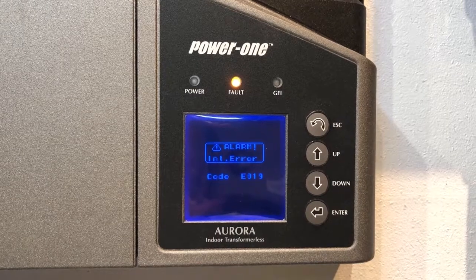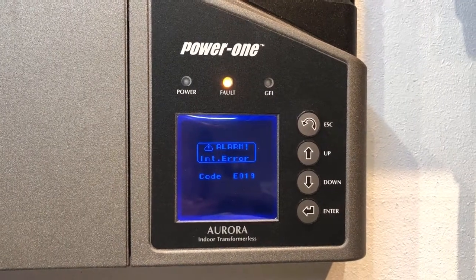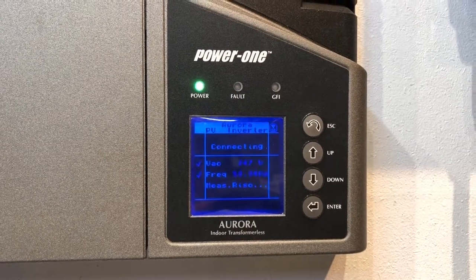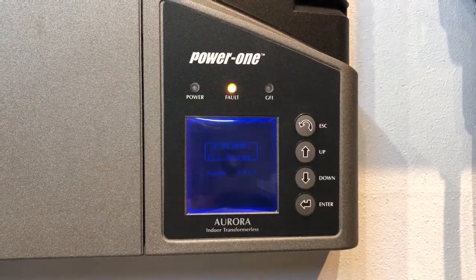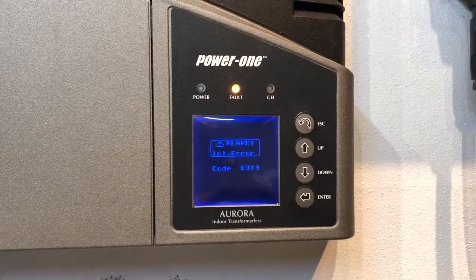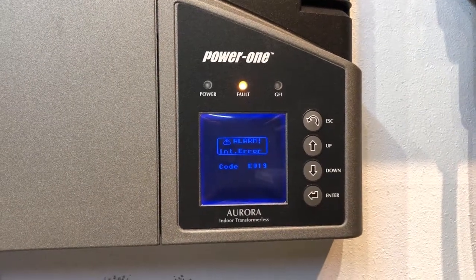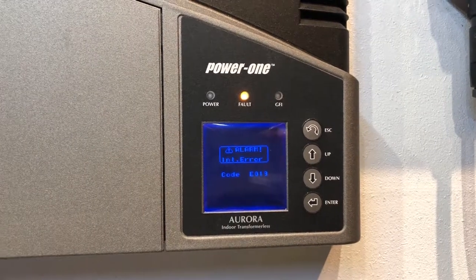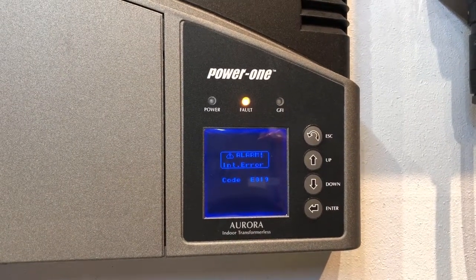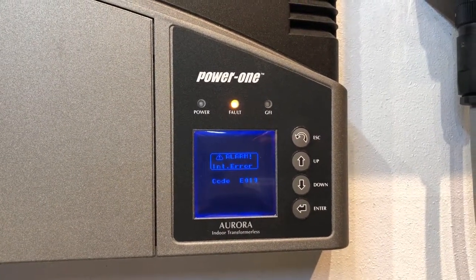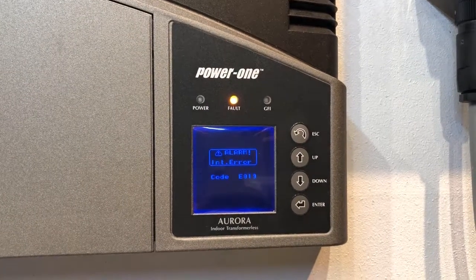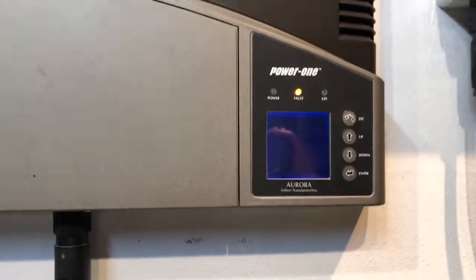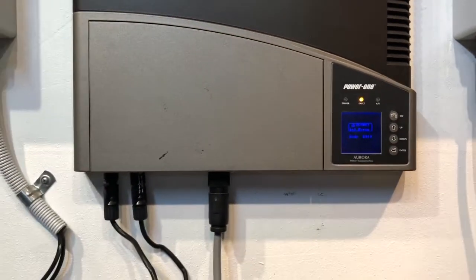In this case, the inverter has an issue that is either going to need the inverter repaired by the manufacturer or replaced. If your inverter is still within the five-year warranty period, it will certainly be covered under warranty. However, we find the Power One Aurora inverters are usually about five years or older by now, so a lot of the time it just works out better to replace it with a good quality new inverter with a full warranty.